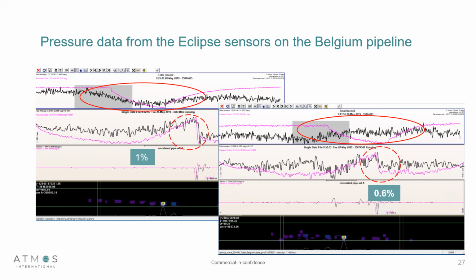As you can see here, as the leak is generated, it creates a negative pressure wave, and both the non-intrusive pressure and intrusive pressure sensor fall. The non-intrusive on this screen is in black and the intrusive is in pink. So this is demonstrating that even though it's not actually physically measuring the product, it's still able to provide very accurate sensitivity, and more importantly, it's still also able to provide very accurate leak location as well.